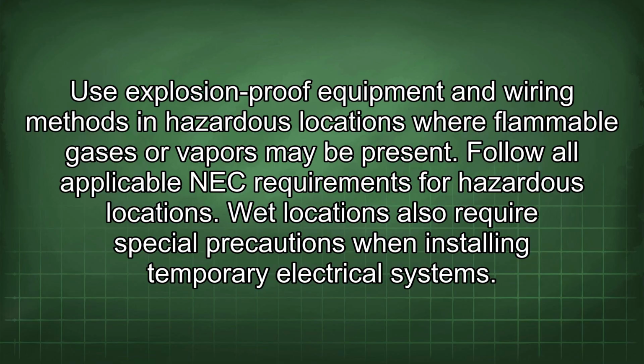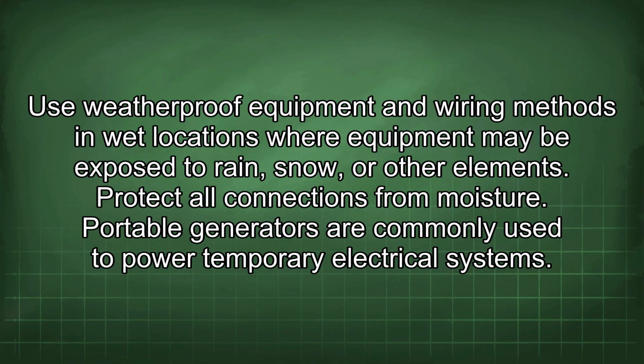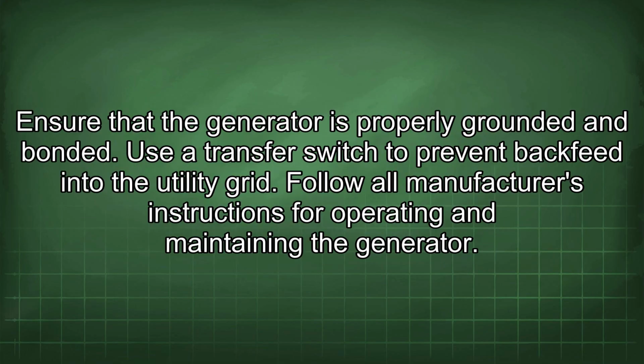Wet locations also require special precautions when installing temporary electrical systems. Use weatherproof equipment and wiring methods in wet locations where equipment may be exposed to rain, snow, or other elements. Protect all connections from moisture. Portable generators are commonly used to power temporary electrical systems. Ensure that the generator is properly grounded and bonded. Use a transfer switch to prevent backfeed into the utility grid. Follow all manufacturer's instructions for operating and maintaining the generator.